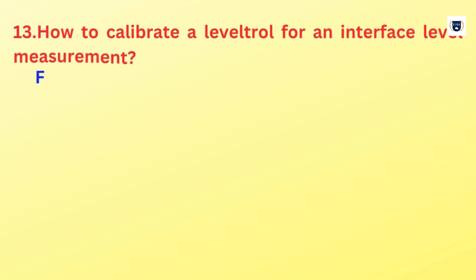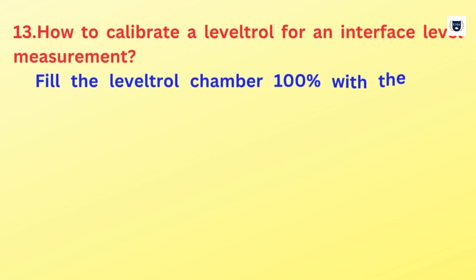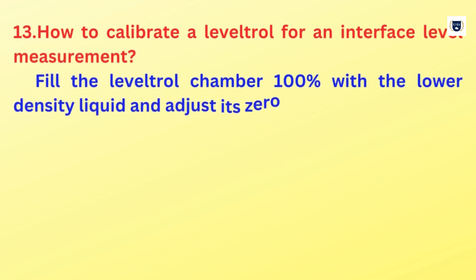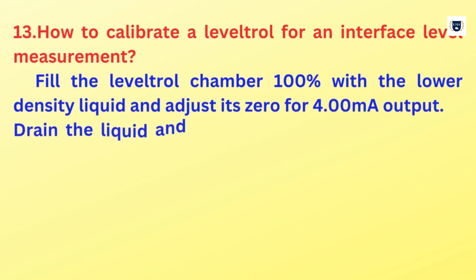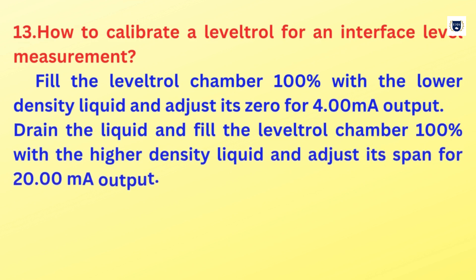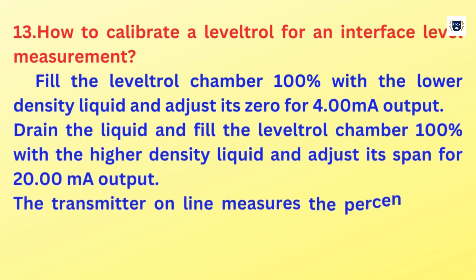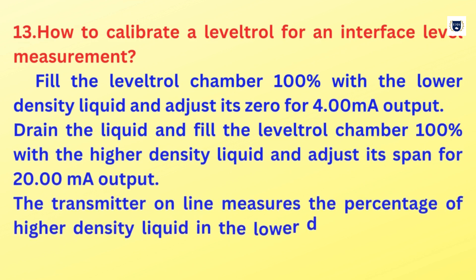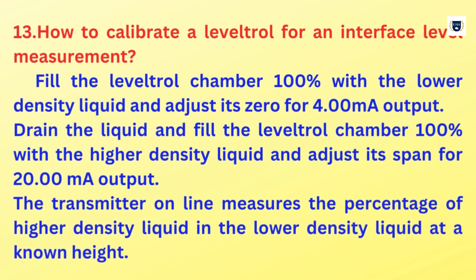How to calibrate a Leveltrol for an interface level measurement? Fill the Leveltrol chamber 100% with the lower density liquid and adjust its zero for 4 milliamps output. Drain the liquid and fill the Leveltrol chamber 100% with the higher density liquid and adjust its span for 20 milliamps output. The transmitter online measures the percentage of higher density liquid in the lower density liquid at a known height.